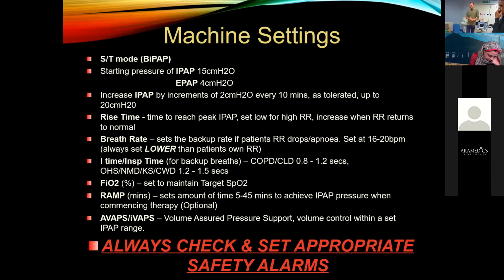Breath rate in the settings is for our backup breath rate. So we said it's ST mode, synchronized timed mode. Timed is a safety function. If our patients become apneic or their respiratory rate suddenly drops, the machine will deliver timed backup breaths for our patient to keep them safe. So breath rate in the settings is whatever respiratory rate you want the machine to make sure your patient maintains if they suddenly become apneic or drop their respiratory rate.